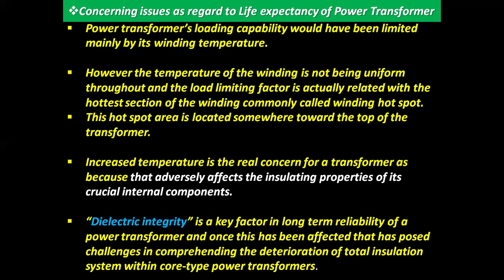Increased temperature is the real concern for a transformer, because it adversely affects the insulating properties of its crucial internal components. Dielectric integrity is a key factor in the long-term reliability of a power transformer. And once this has been affected, it poses challenges in comprehending the deterioration of the total insulation system within core type power transformers.